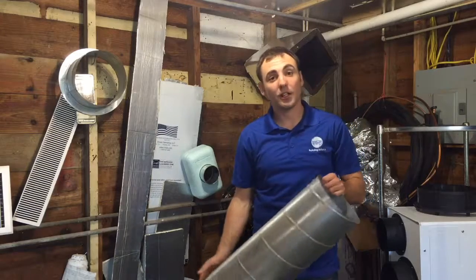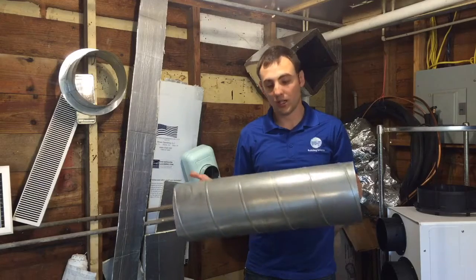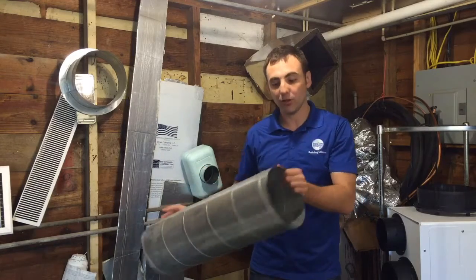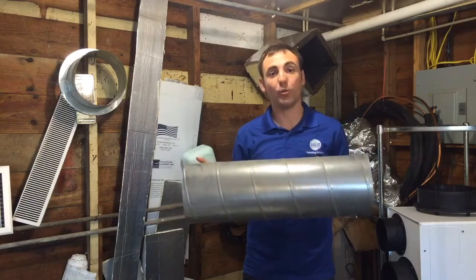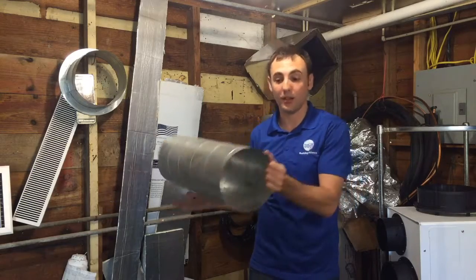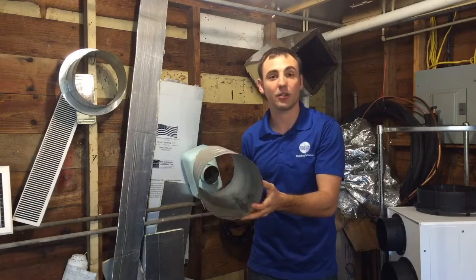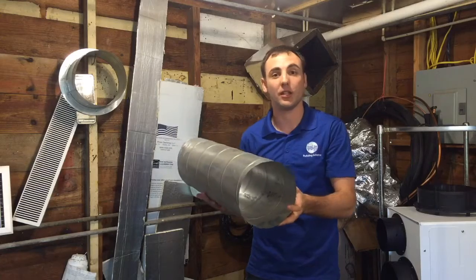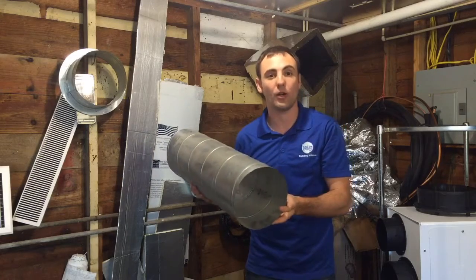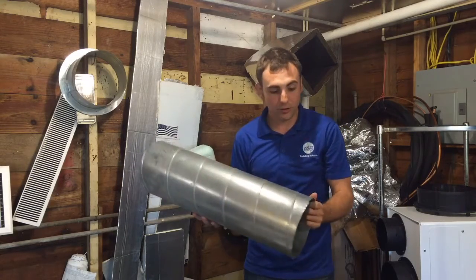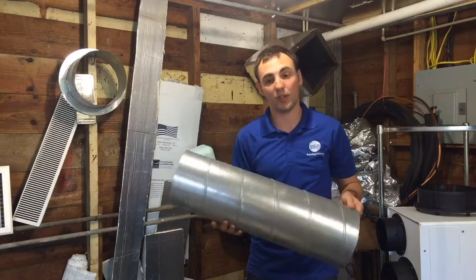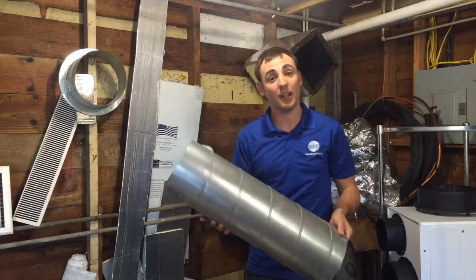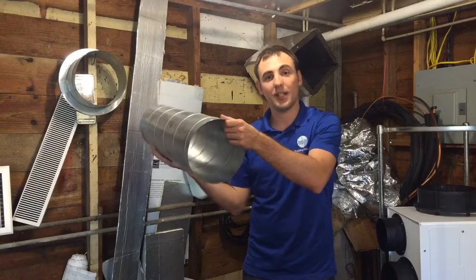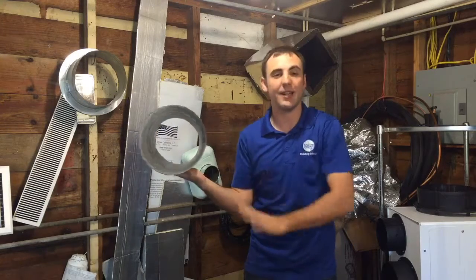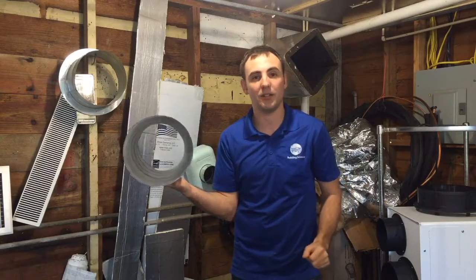Alright, so we can now talk a little more about different types of ductwork. This is called metal spiral duct. This works really good when it's in conditioned space, because as you'll see, there's no insulation on this duct, so it has to be in conditioned space, otherwise it's going to condense and there's going to be all sorts of air quality issues down the road. Also, there's lots of duct leakage that's associated with this. This is not airtight. But it's okay, because if this duct is in conditioned space, then whatever air leaks out goes into the conditioned space, and it's totally fine.